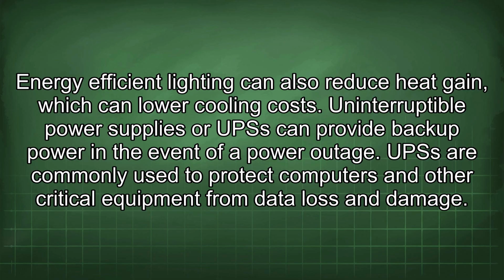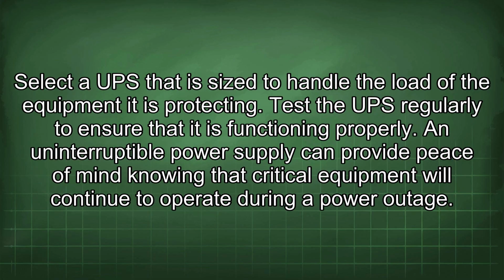Uninterruptible power supplies, or UPS, can provide backup power in the event of a power outage. UPS are commonly used to protect computers and other critical equipment from data loss and damage. Select a UPS that is sized to handle the load of the equipment it is protecting. Test the UPS regularly to ensure that it is functioning properly. An uninterruptible power supply can provide peace of mind knowing that critical equipment will continue to operate during a power outage.